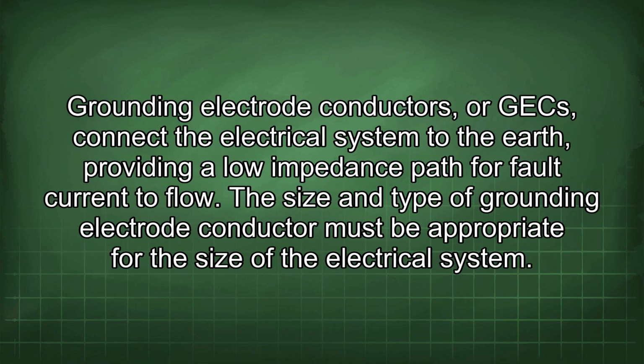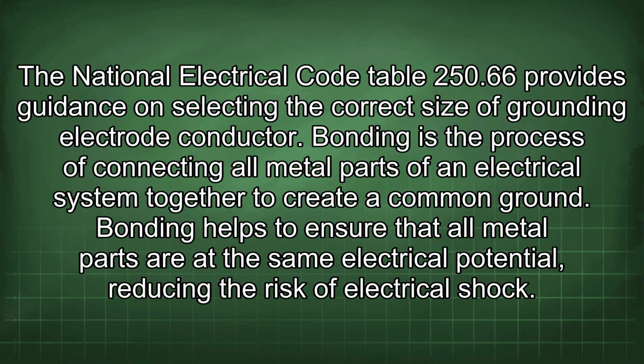Grounding electrode conductors, or GECs, connect the electrical system to the earth, providing a low impedance path for fault current to flow. The size and type of grounding electrode conductor must be appropriate for the size of the electrical system. The National Electrical Code Table 250.66 provides guidance on selecting the correct size of grounding electrode conductor. Bonding is the process of connecting all metal parts of an electrical system together to create a common ground.